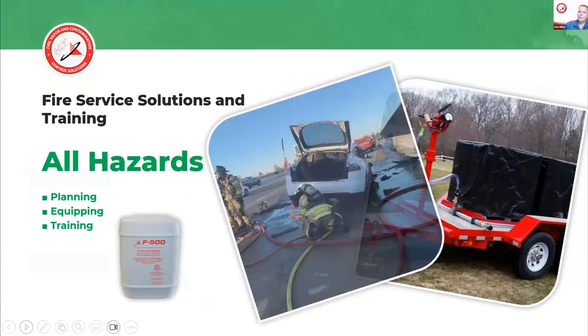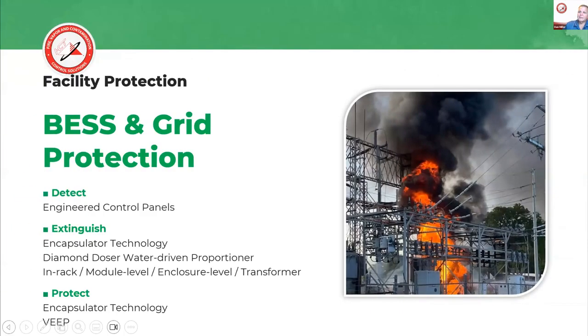We can encapsulate those gases inside the unit, and that's part of the Encapsulator system at the enclosure level. As fire grows and produces gases, we can detect those gases and activate the Encapsulator system to keep the gases down and keep it from exploding on responders.